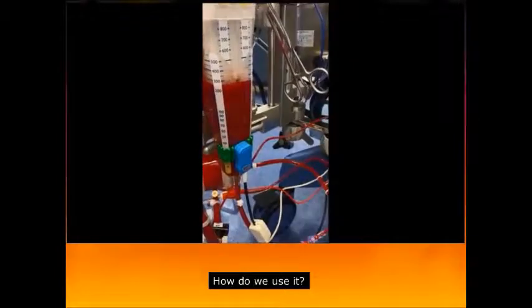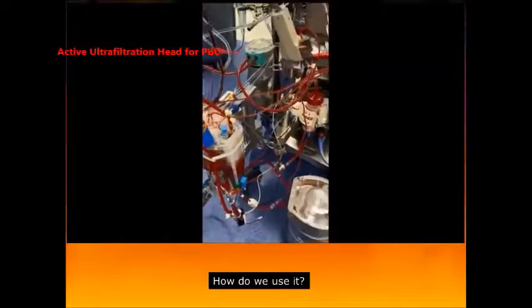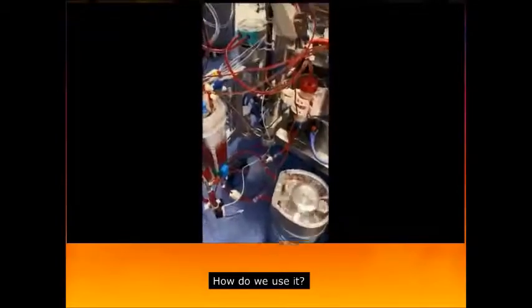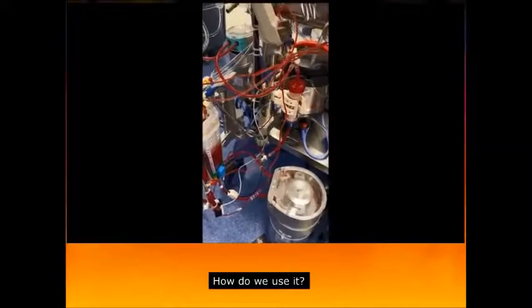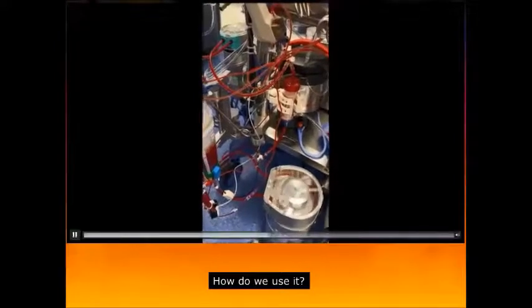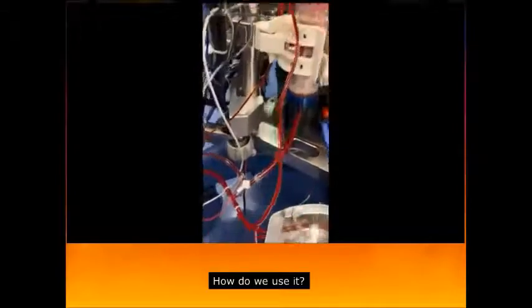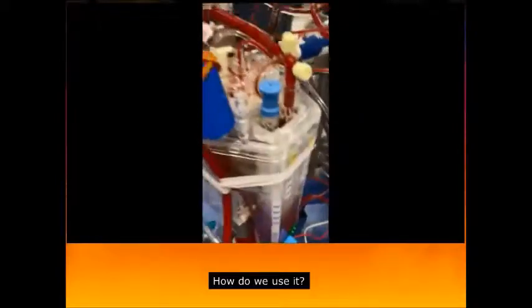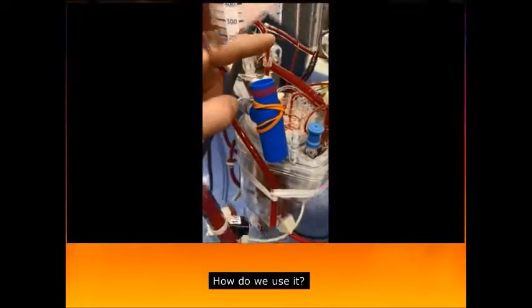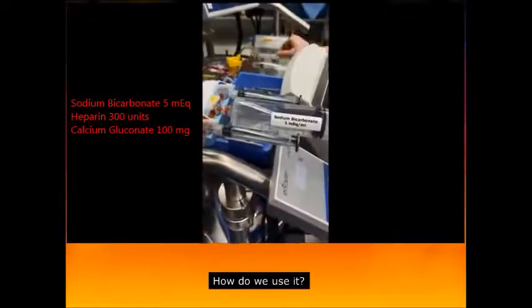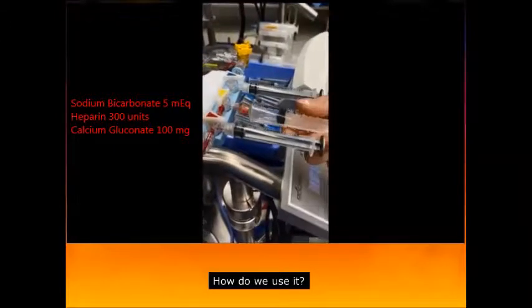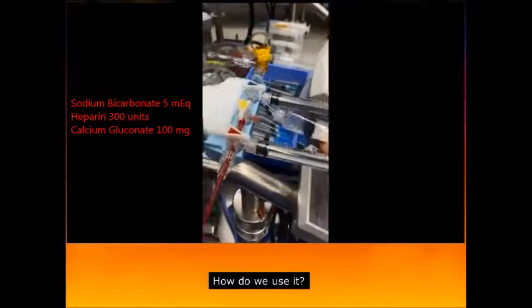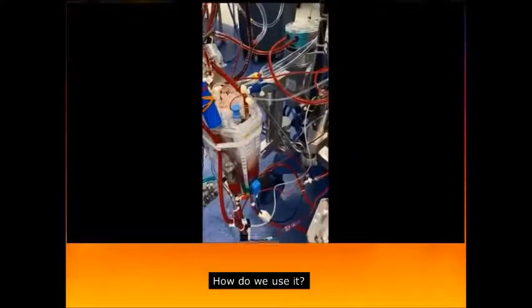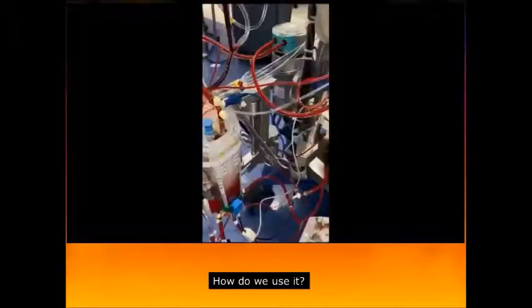The ultrafiltration head is turned on and the ultrafiltrate line is removed. The volume is taken back down to 75 milliliters. As a reminder, the flow path is from the venous line to the ultrafiltrate head to the ultrafilter top, out the bottom, to a stopcock that connects to a line which returns to the reservoir. Once the volume is down, 5 milliequivalents of bicarb is added, followed by 300 units of heparin and 100 milligrams of calcium gluconate. The ultrafiltration head is eventually turned off and a prime blood gas is sent.